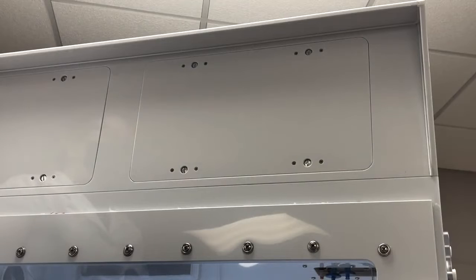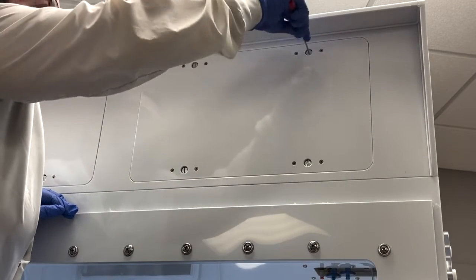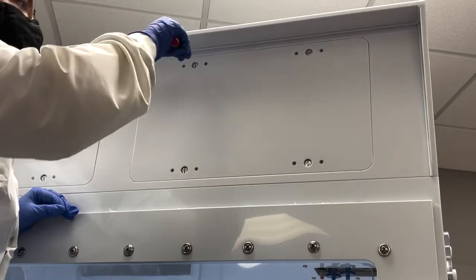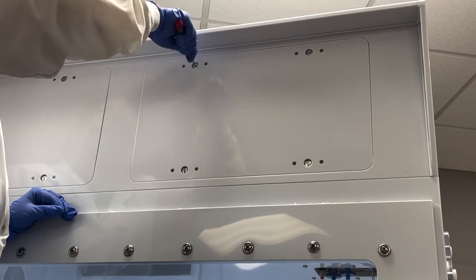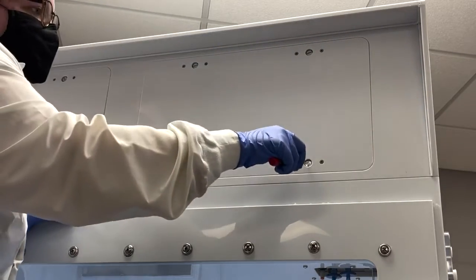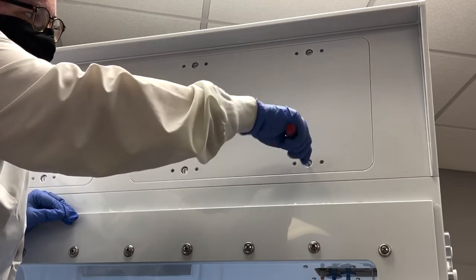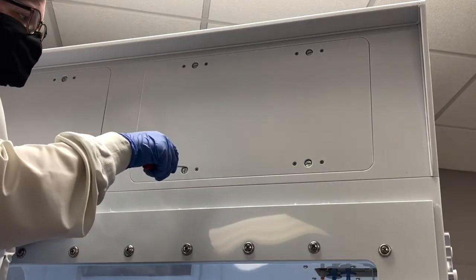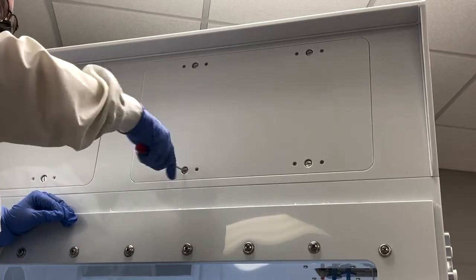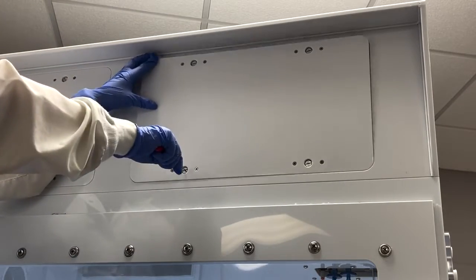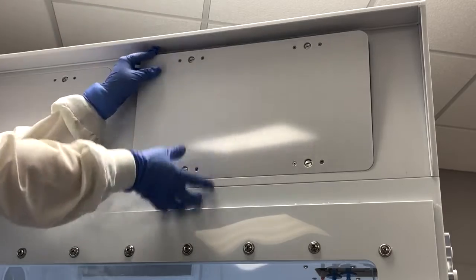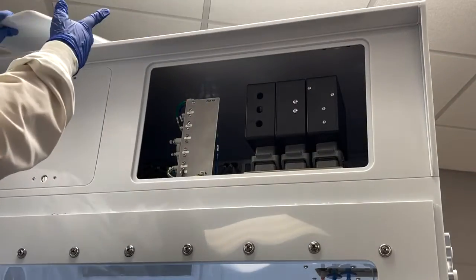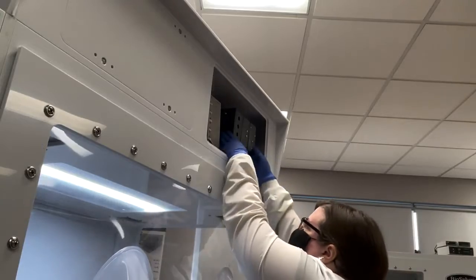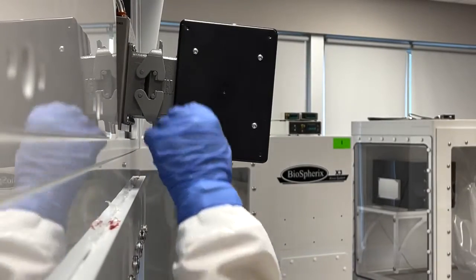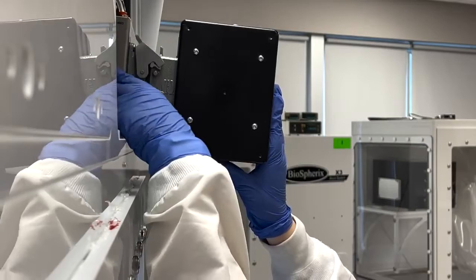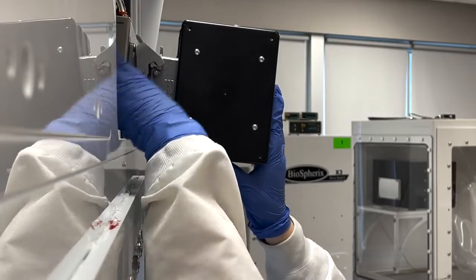Using a flathead screwdriver, unlock all screws on the panel by turning them counterclockwise. Once the screws are unlocked, remove the panel and set it aside. For easier access, the whole pod assembly can be flipped down toward the user. On the sensor pod you need to change, unclip both connectors holding it into the sensor assembly.